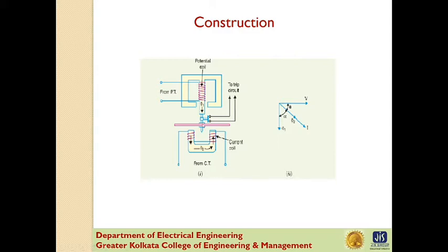The spindle of the disc carries the moving contact which bridges with the fixed contacts when the disc has rotated through a preset angle. By adjusting this angle, the travel of the moving contact can be adjusted and hence any desired time setting can be given to the relay.